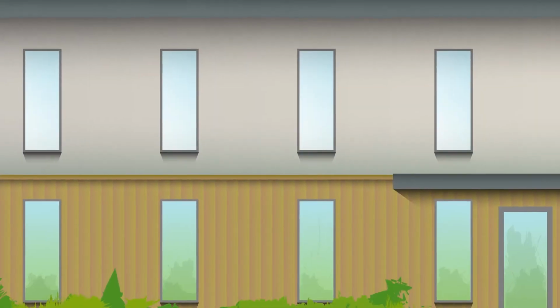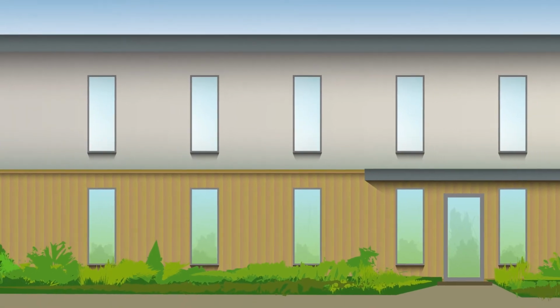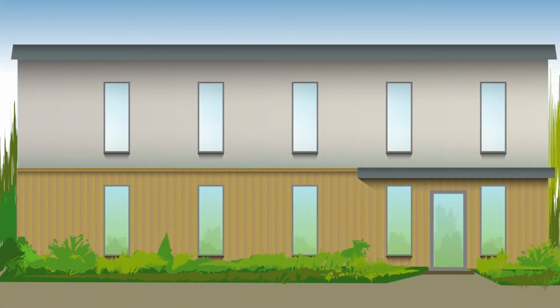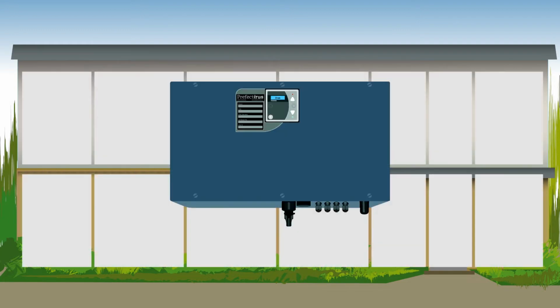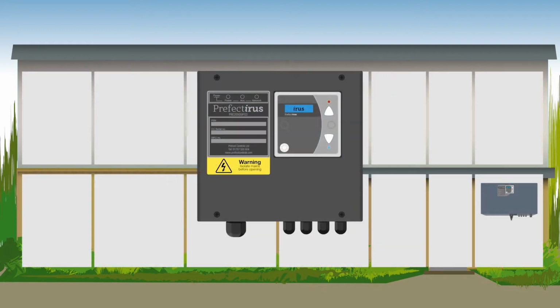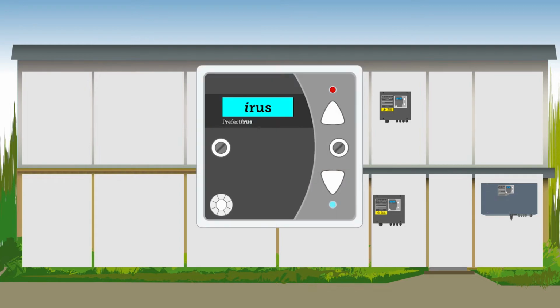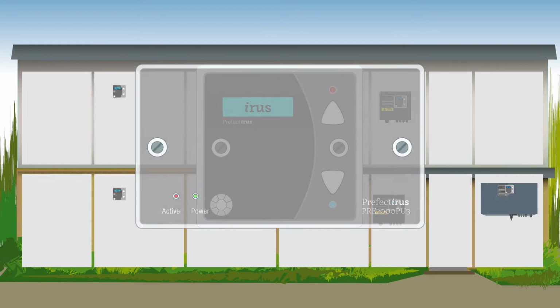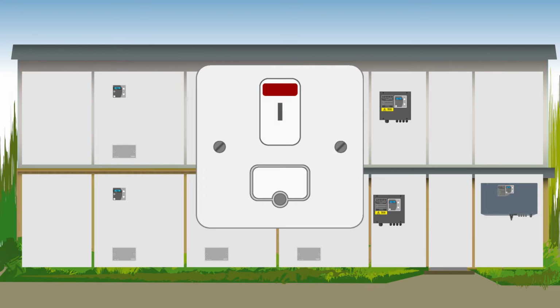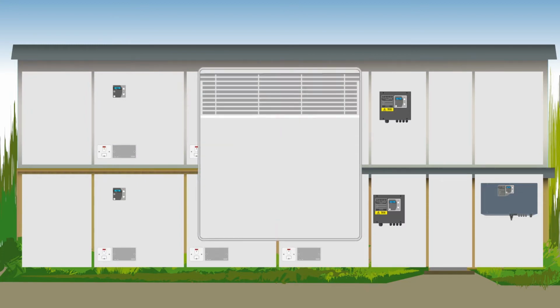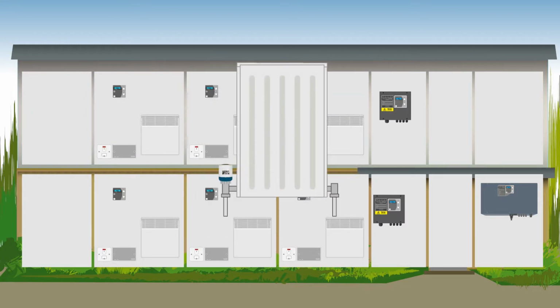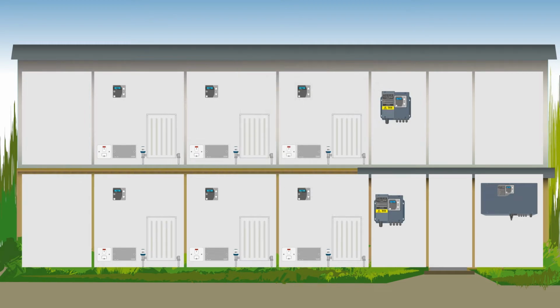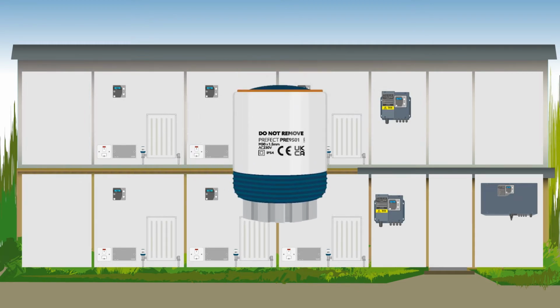Irus is a centrally controlled energy management system for multi-occupancy dwellings, such as student accommodation. It comprises a master interface unit situated in or close to the comms room, and secondary interface units situated in designated electrical riser cupboards around the site. Each room requires a control unit, a power unit, a key-switched fuse spur, and the heat source, electric heaters or wet radiators. If wet radiators are installed, a valve actuator is also needed.